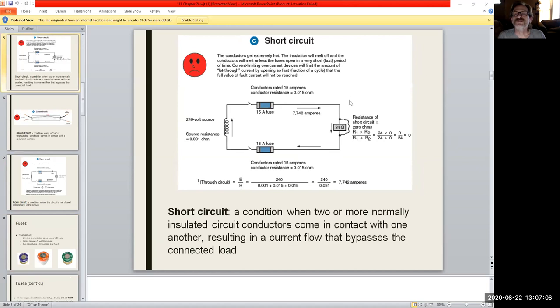So what do we experience when we get a short circuit? Well, a short circuit would be a hard short where somewhere along the line the wiring has become crossed together. Maybe insulation was bare or stripped. What ends up happening is it's bypassing this device altogether. And the way current works is it'll follow the path of least resistance. So it'll flow, but it likes to flow to the easy spots. He's lazy. He wants to go wherever it's the easiest way, and it will.